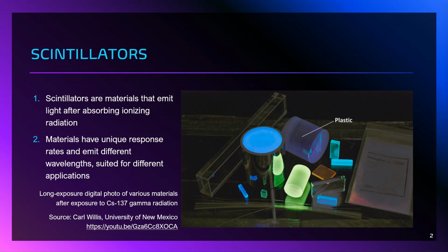And what's happening with the scintillator is that the material's absorbing the radiation, the X rays or gamma rays or heavy particles, where the photon energy is transmitted via photoelectric effects and Compton scattering or pair production, and the energy is transferred to the charged particles, creating a large number of excited electrons and electron holes during that absorption process.